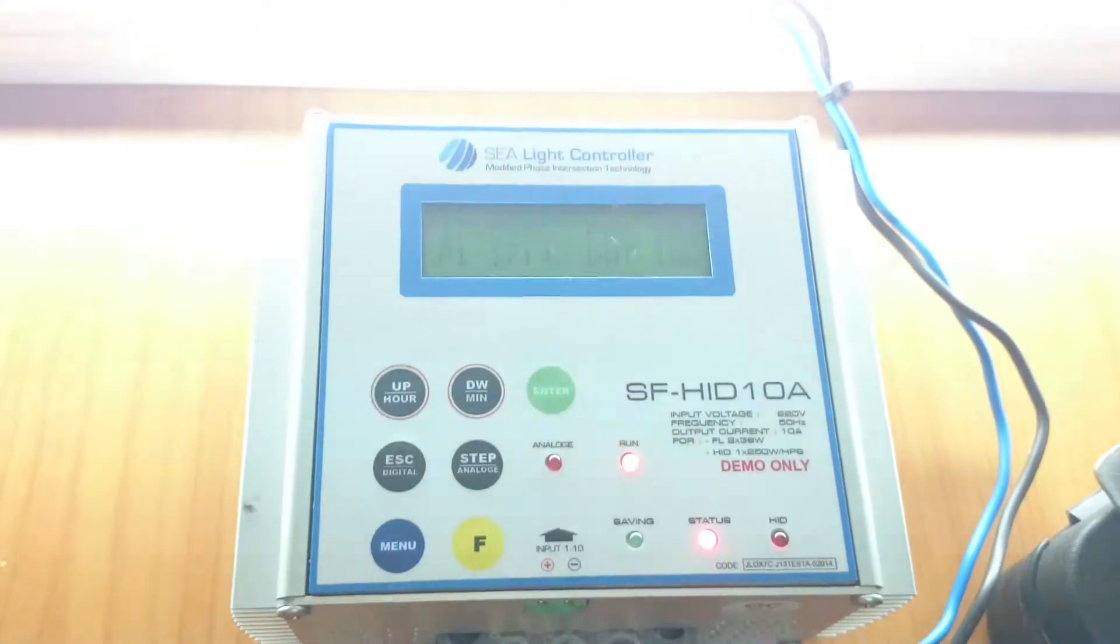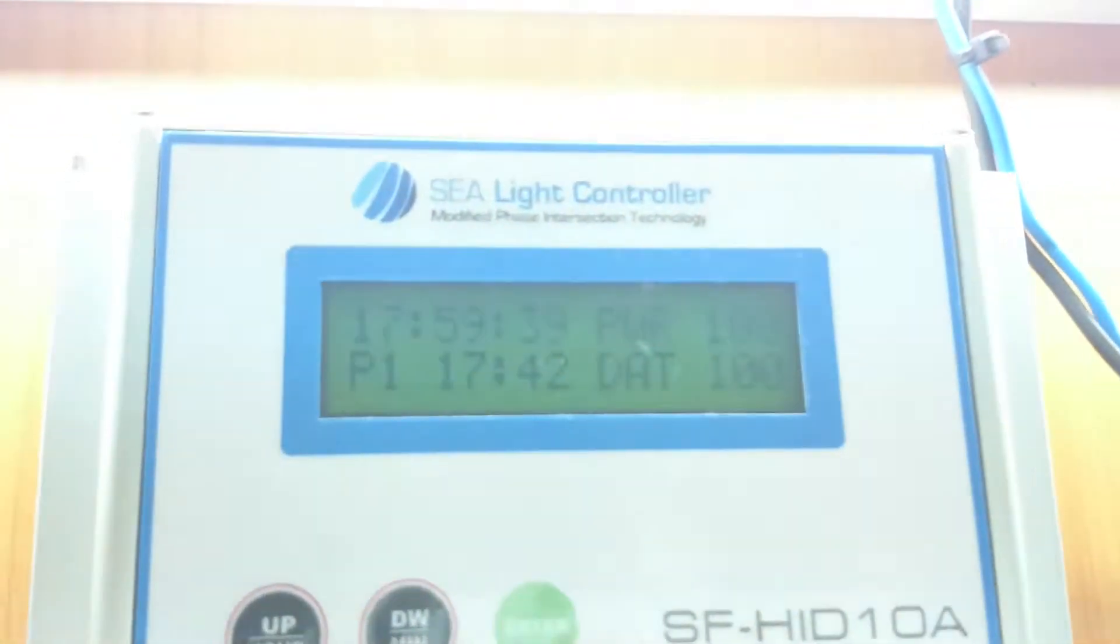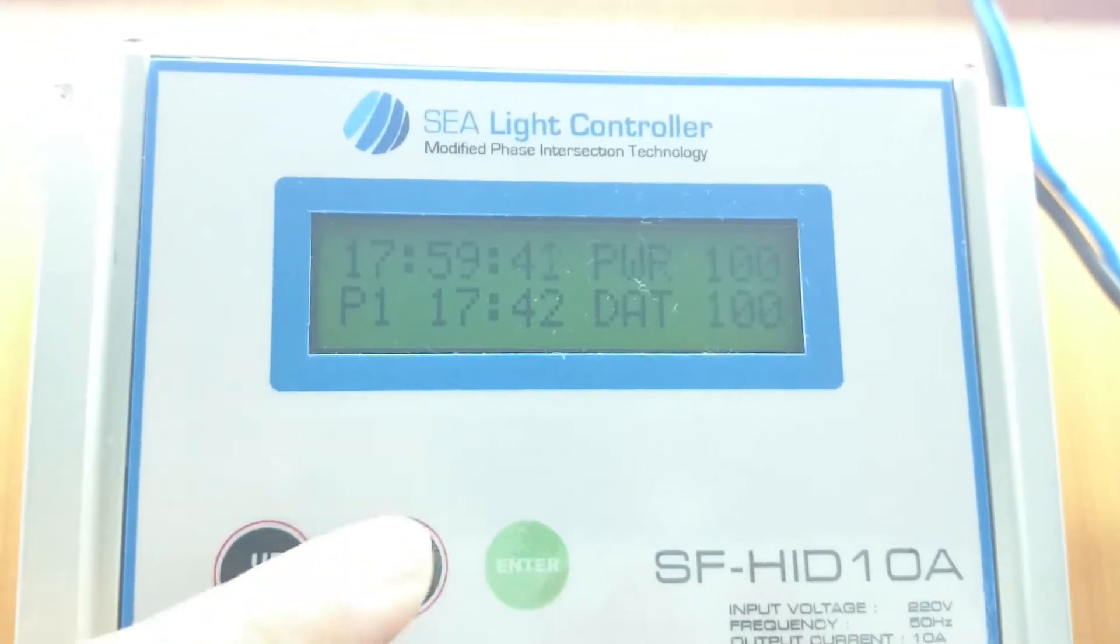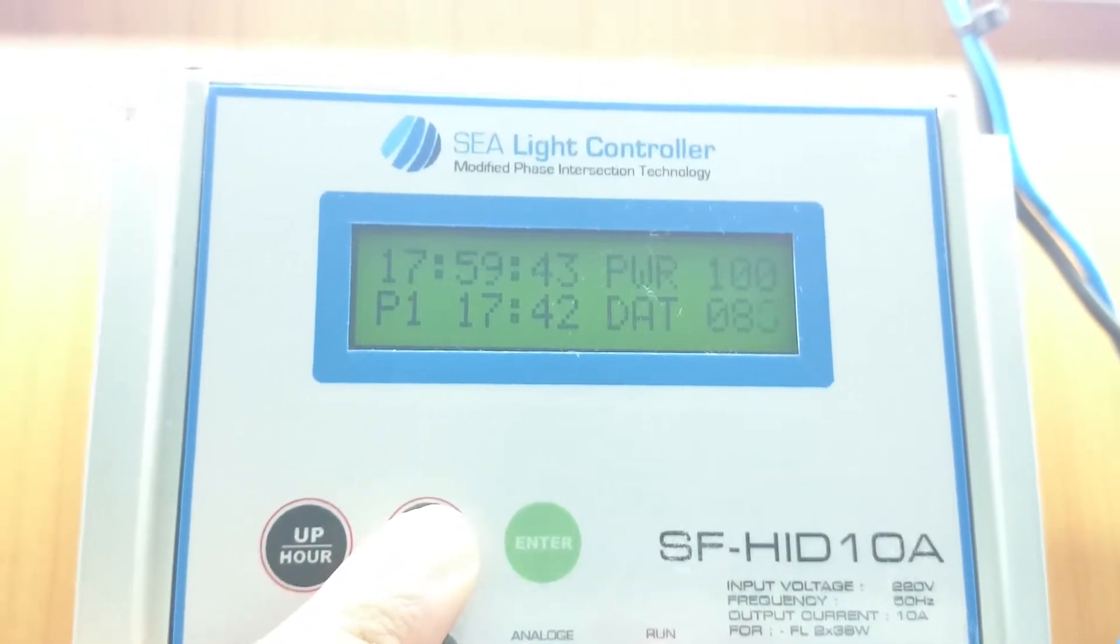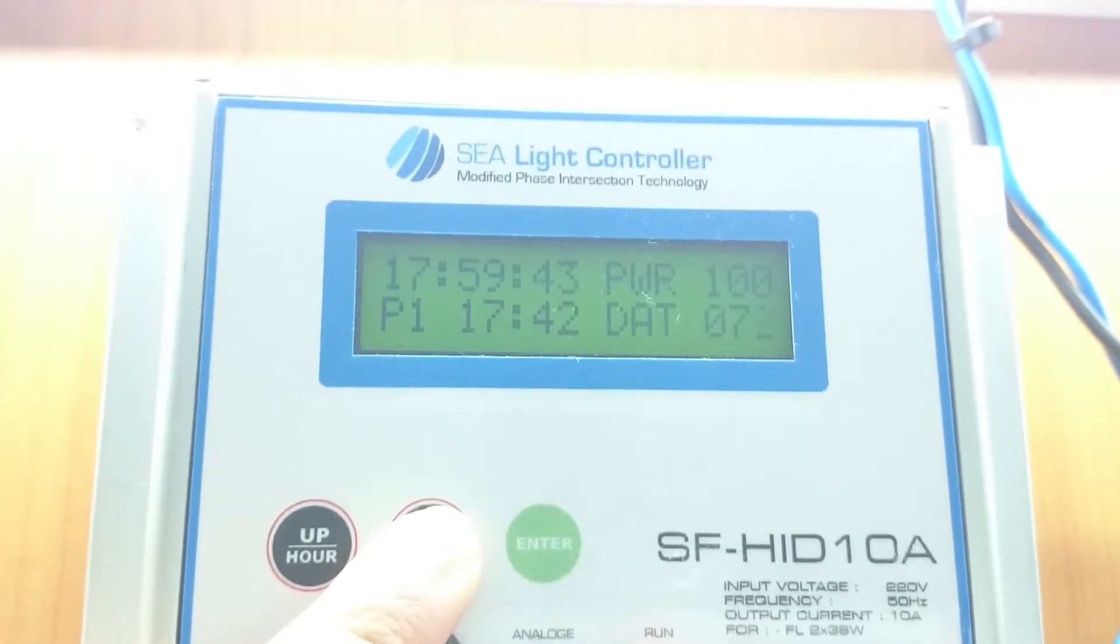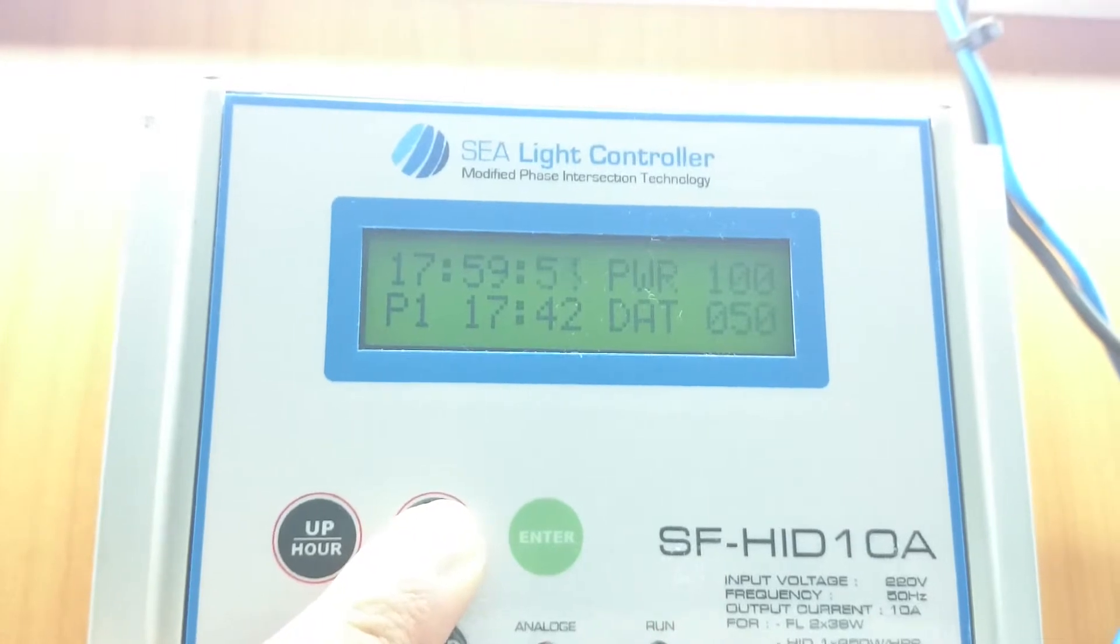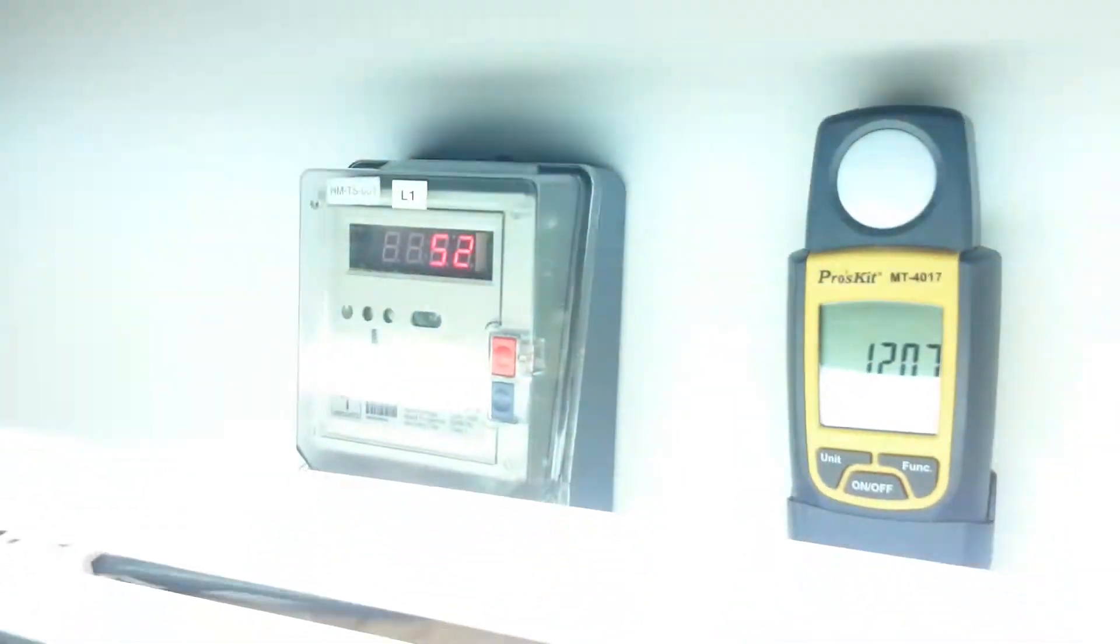Now I will give you a demonstration of the SEA Light controller in action. As you can see right now it's at 100% power. Let's reduce that down to the minimum 50% level. And then we will be monitoring the power consumption and the brightness. This will take a while for it to go down all the way to 50%. If we were to immediately reduce the power to 50% then it would damage the lamp so it happens at a very gradual rate.